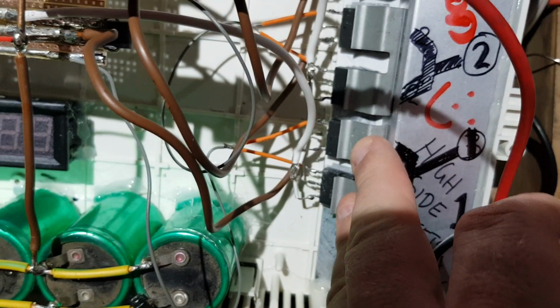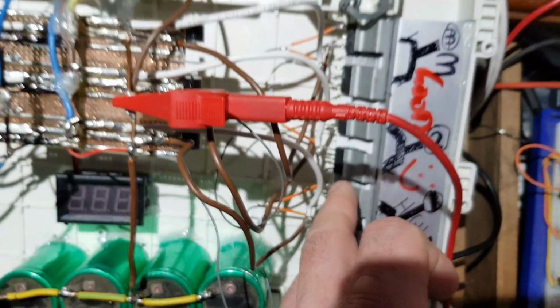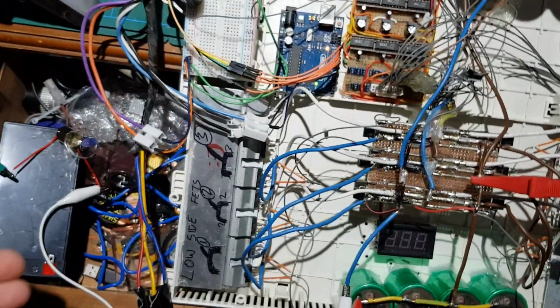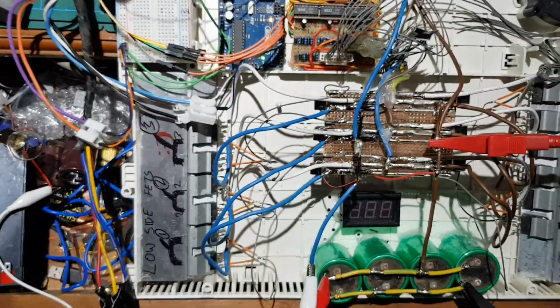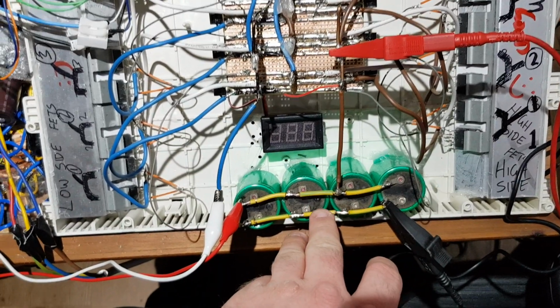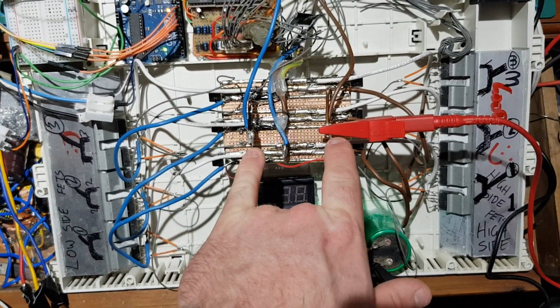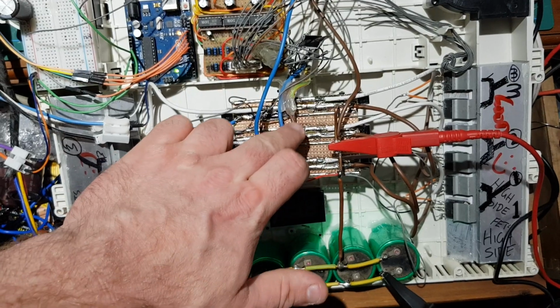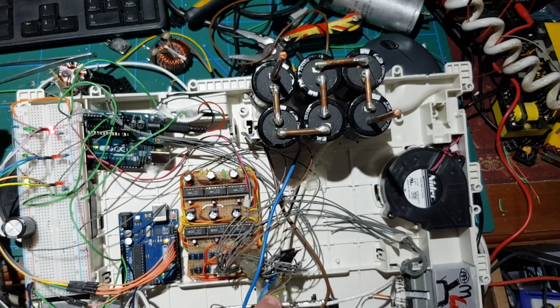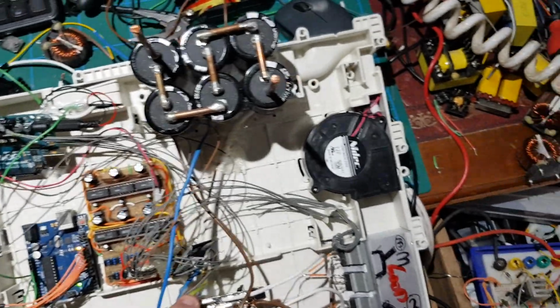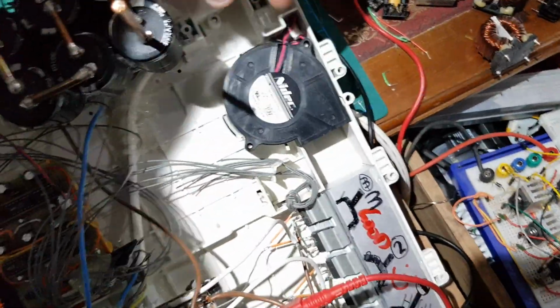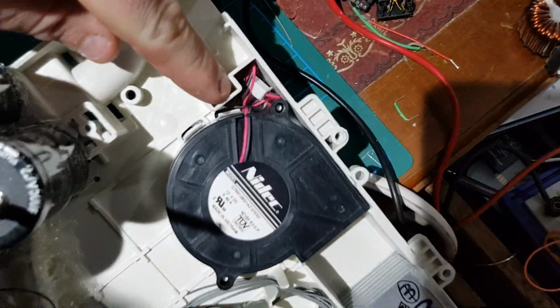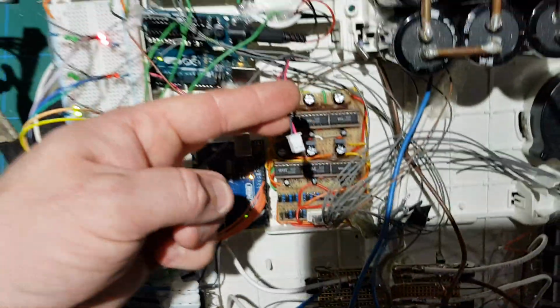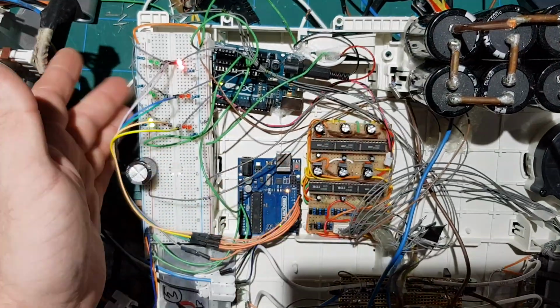So these two are essentially one transistor, just doubling up on the current. So there's three there and three there. And what I've got also is DC bus capacitors that are underpowered, underrated. DC bus, three phases out, which gives you your AC three phase. And cooling fans, which are not operational at the moment. That's just tucked in there. And there's the wire for the other one. There's another cooling fan under here.